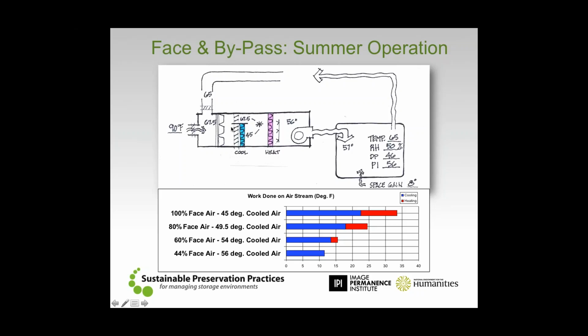But we realize that if we keep tinkering and adjusting these face and bypass dampers, our sweet spot is that if we send 44% of the total air volume over the cooling coil, and we allow that to blend with the 67.5 degrees air that is bypassed on the other side, we wind up with a 56-degree mixed air condition on the other side of the cooling coil that matches exactly the supply air condition that we need to send out to the space. Which means now I get the exact same temperature and set point condition in the room as what I had in this scenario. But instead of using 33, 34 degrees worth of total energy at these coils to achieve that, now I'm using about 12 degrees worth of cooling energy here at the coil, and my reheat is now free because I found the right blend of those conditions.